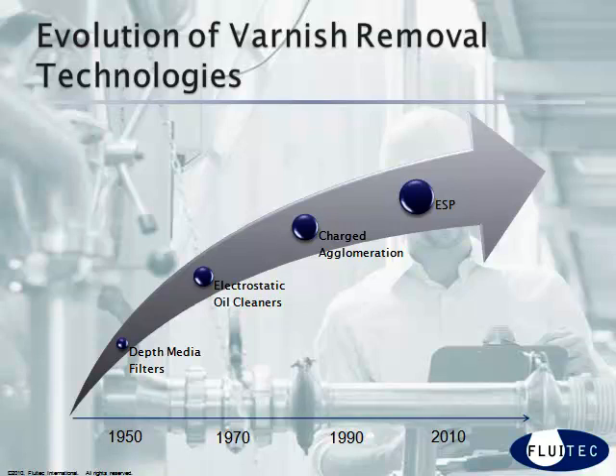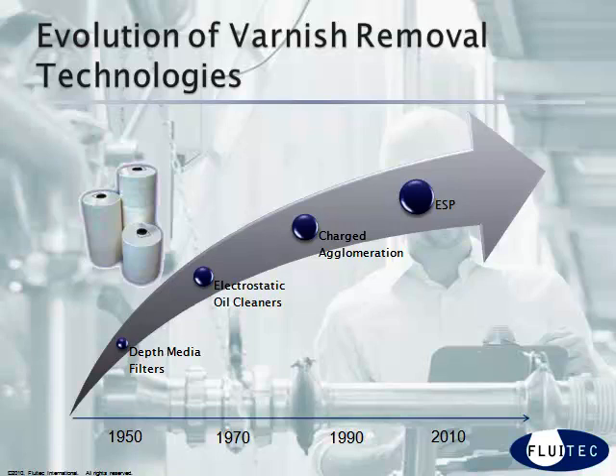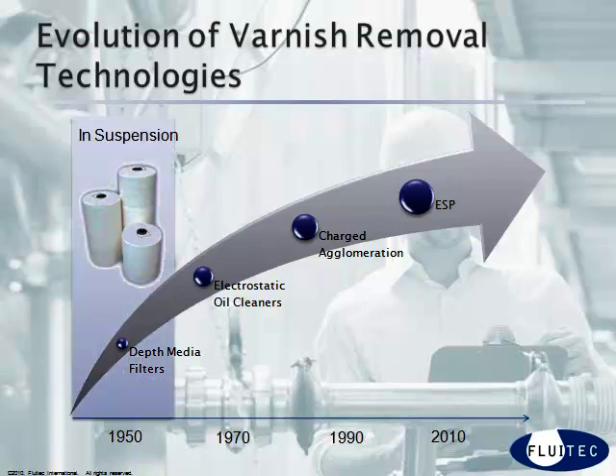Following are brief descriptions of each technology. Depth media filters do not filter out submicron contaminants, but rather have the ability to absorb them onto their filter media. This technology is simple but effective. They are only designed to remove contaminants in suspension, however. If you are using this technology to treat cool oil, it is important to change the filters out before the oil warms up, or else the contaminants will go back into solution, re-polluting the system. This is known as soft contaminant leaching.